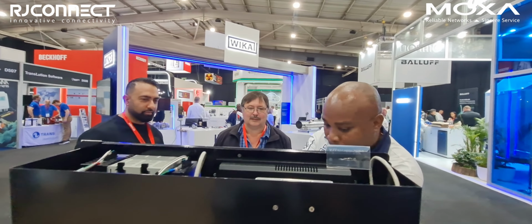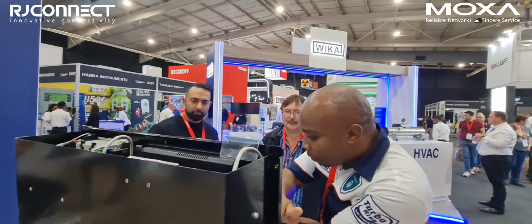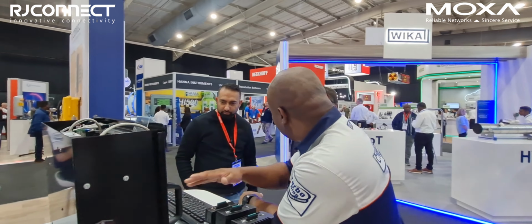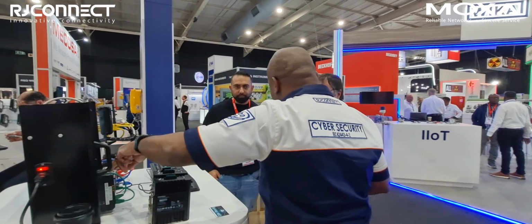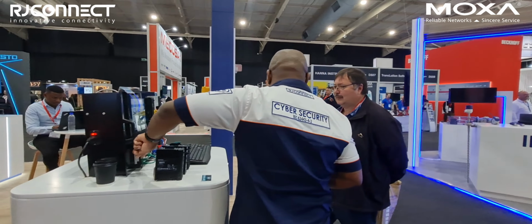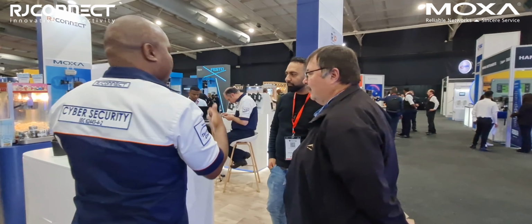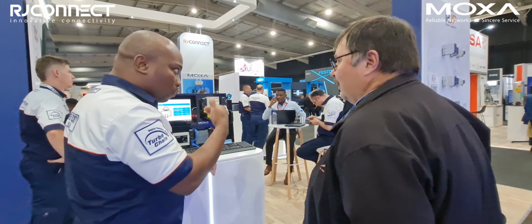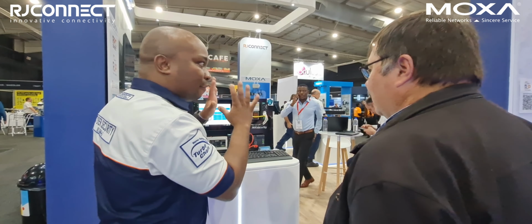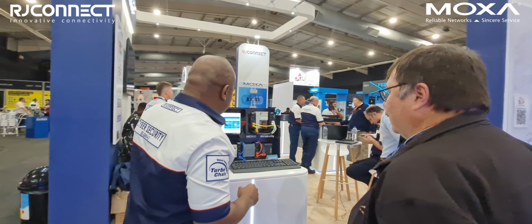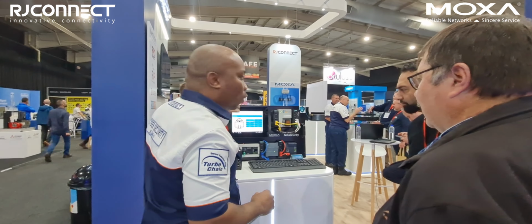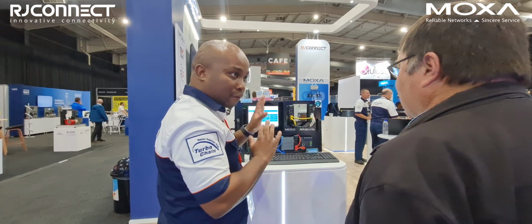So you have a PLC, and then you just deploy that firewall next to it. Its primary objective is to protect this PLC. So when someone wants to log into this PLC, they'll have to log in through the firewall. And on this device, you can set up whitelisting, where you say this person with this profile can only view, and this person with this profile can configure, make changes, and all of that. And whatever happens here, we'll send you a notification and let you know if there's an attack.